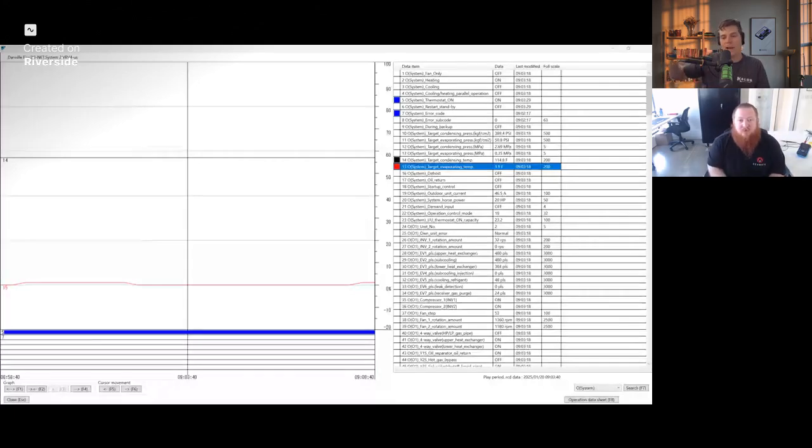So when we talk about F3, it's important to remember that F3 is actually different per model. When we talk about VRV3, F3 is actually a malfunction of the discharge pipe thermistor. However, as we get into the later generation series, we're going to get into an F3-01. The 01 sub error codes were added in VRV4 and on, and that 01 error code actually means something different. It's not a faulty thermistor.